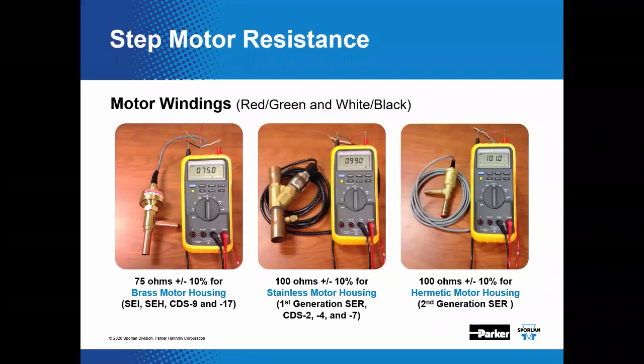But you notice here we have some valves that have a 75 ohm resistance level across the leads. You would check that in pairs, white and black, red and green. And in between opposing pairs, you would have an open circuit. You should have an open circuit to the body of the valve itself. We should hope. You should hope if you want it to work. Yes. And then you notice we have 100 ohm resistance motors in several of our valve lines.